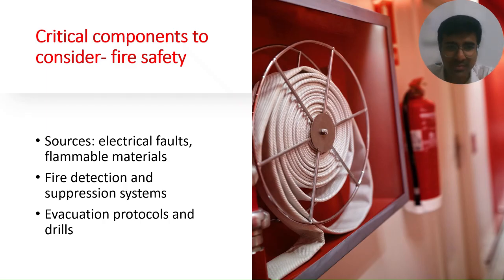Same concept. Fire detection and suppression systems must be up to date. Fire detection system is the main thing that alerts the whole OT or hospital that there is a fire happening in one of your closed operation theaters. Suppression systems are usually water based - you would have seen that sprinklers, when they open, water comes down. Some OTs are designed so that inside the OT there will be no fire sprinklers, because mainly the equipment will get damaged.